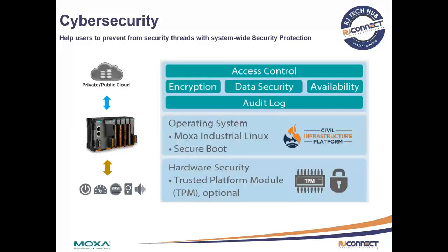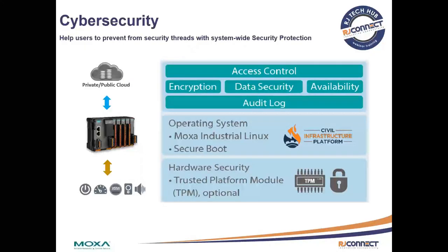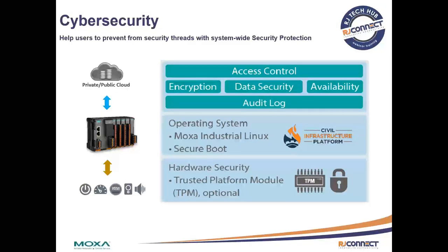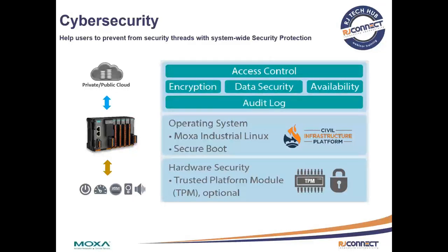And the ioThinx 4533 has cybersecurity that is designed from hardware and operating system to the application level. For hardware level, ioThinx 4533 supports trusted platform modules. For operating system, ioThinx 4533 supports Moxa Industrial Linux, and it has a secure boot. And in application level, ioThinx 4533 is in compliance with IEC 62443-4-2 level 2, which is to ensure that the data is encrypted and secured.